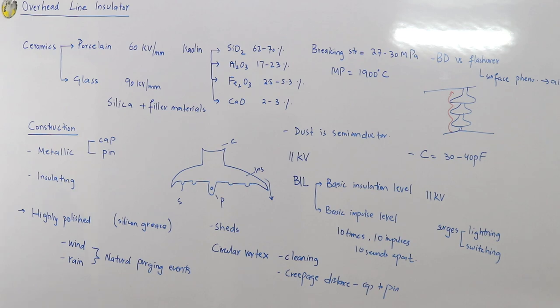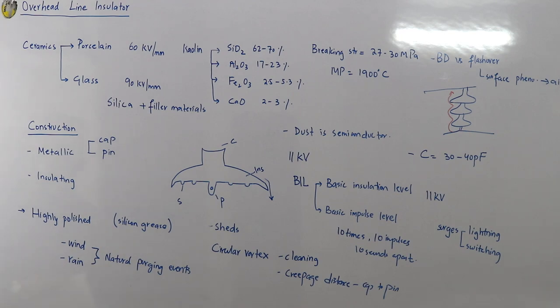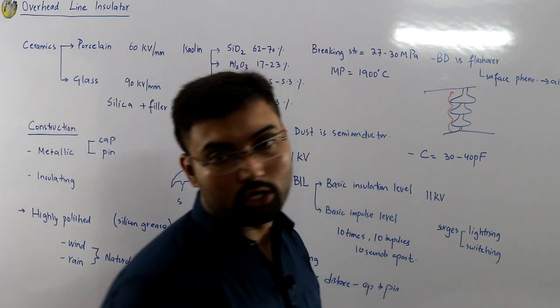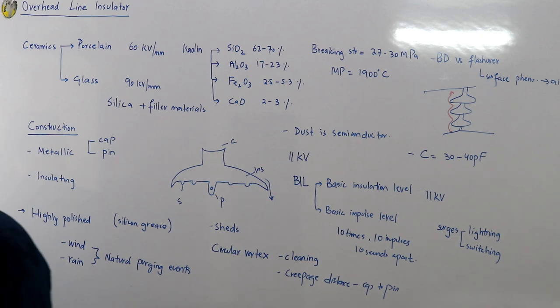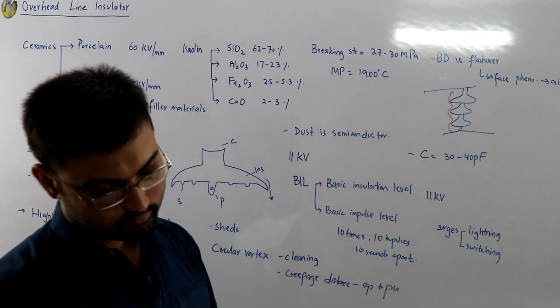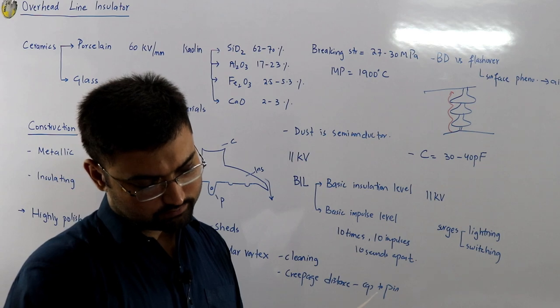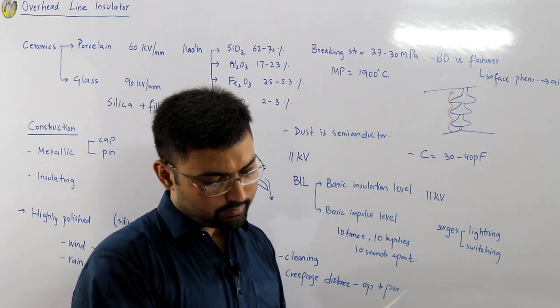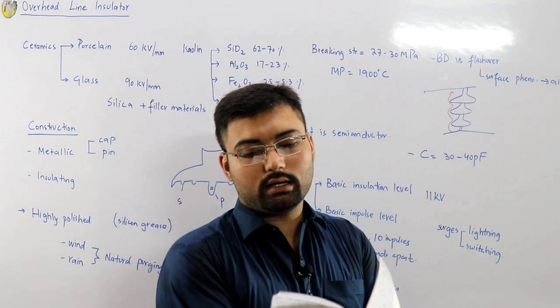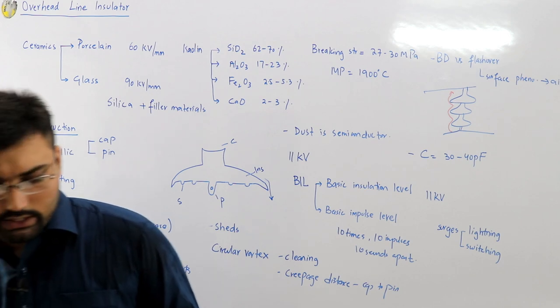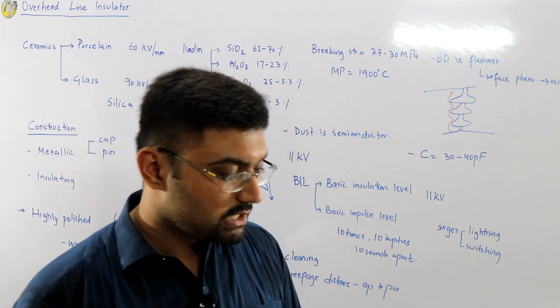To summarize: flashover is a temporary line-to-ground fault, whereas failure or breakdown is a permanent fault. Breakdown versus flashover and flashover's role in single line-to-ground faults are the key distinctions.